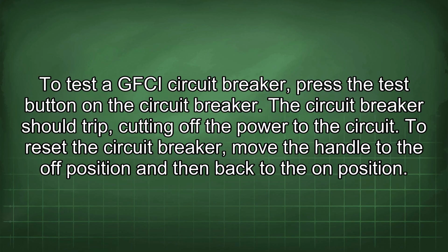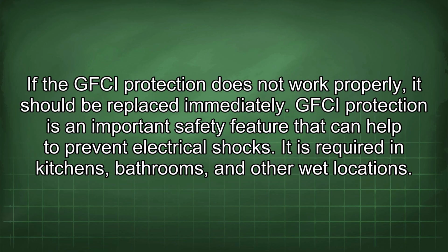To test a GFCI circuit breaker, press the test button on the circuit breaker. The circuit breaker should trip, cutting off the power to the circuit. To reset the circuit breaker, move the handle to the off position and then back to the on position. If the GFCI protection does not work properly, it should be replaced immediately.